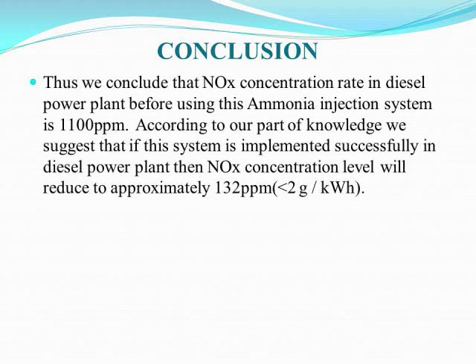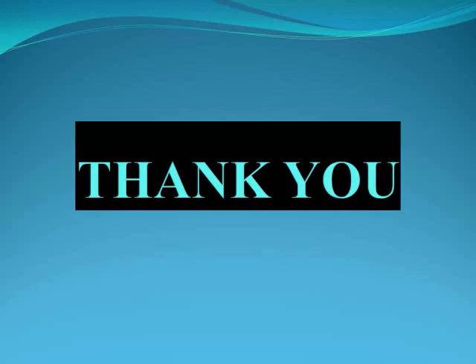Conclusion: We conclude that NOx concentration in the power plant before using the ammonia injection system is around 1100 ppm. According to our report, if we implement the SCR system successfully in this power plant, the NOx concentration level will reduce to approximately 130 ppm, which is less than 2 grams per kilowatt hour. Thank you.